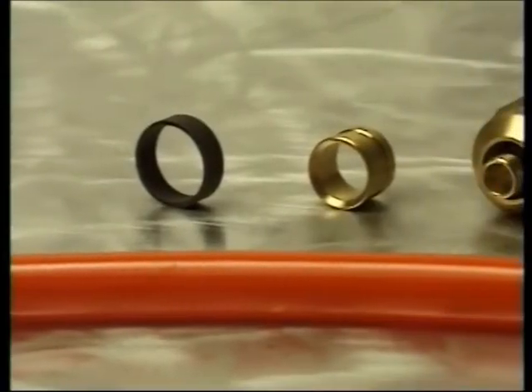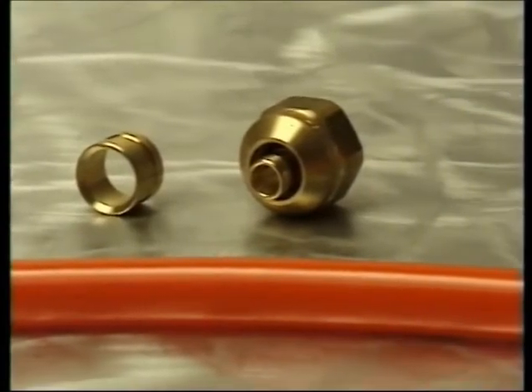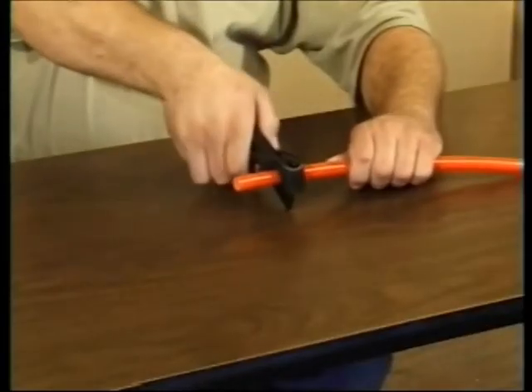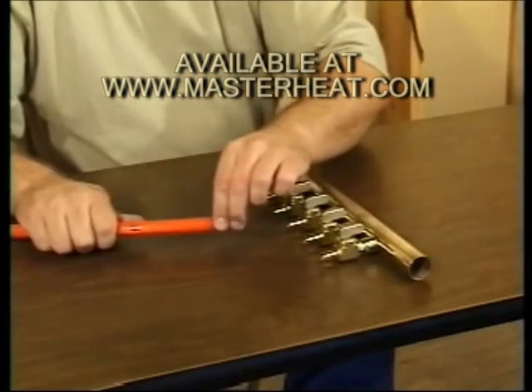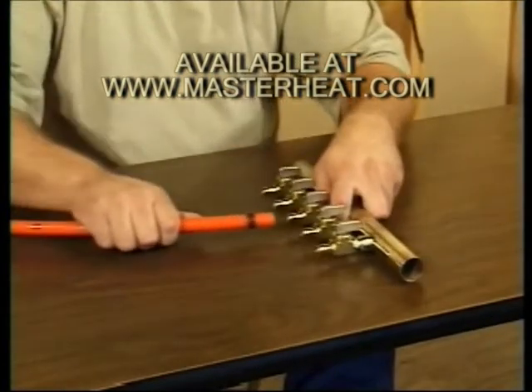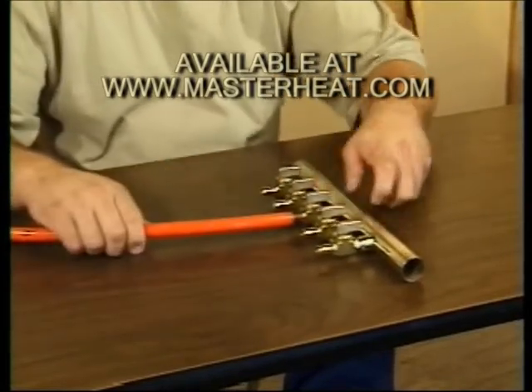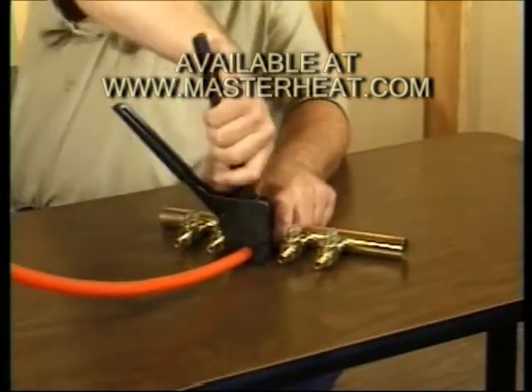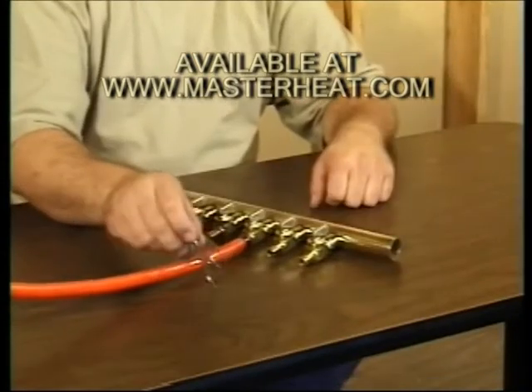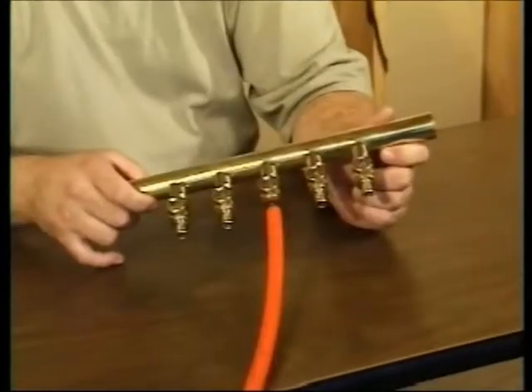PEX has three connection options: crimp ring, slide lock, and compression. Our most popular is the crimp ring. To make a connection, first cut the epex with a 90 degree square cut. Slide the proper sized copper crimp ring over the tube, push the tube onto the crimp ring fitting, and then slide the crimp ring over the barb. Use the proper sized crimping tool to compress the ring until the tool bottoms out. Use the crimp ring go no-go gauge to make sure the fitting is sized correctly.